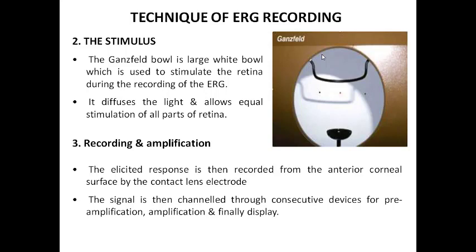The second requirement of ERG is the Ganzfeld bowl stimulator. The Ganzfeld bowl is a large white bowl used to stimulate the retina during recording of ERG. It diffuses the light and allows equal stimulation of all parts of the retina. Regarding recording and amplification, the elicited response is recorded from the anterior corneal surface by the contact lens electrode or any other type of electrode. The signal is then channeled through consecutive devices for pre-amplification, amplification, and finally display.